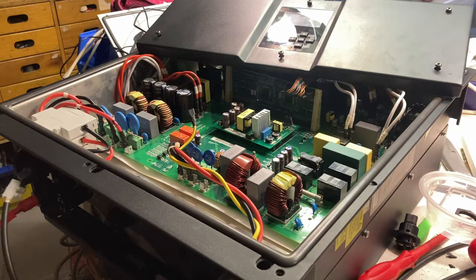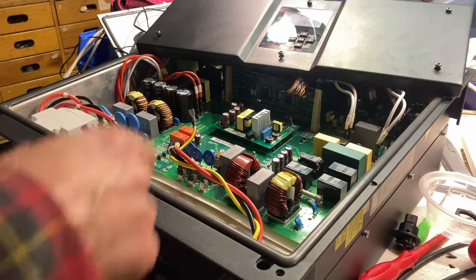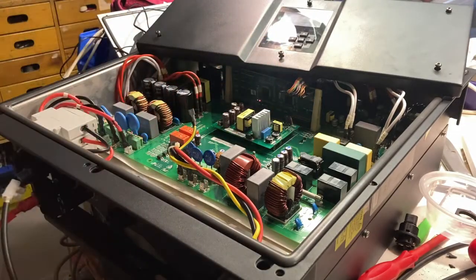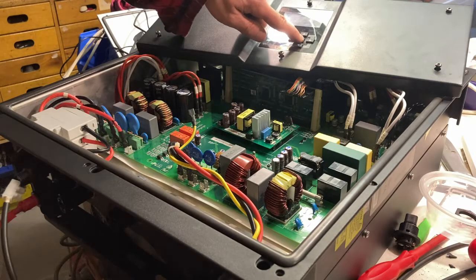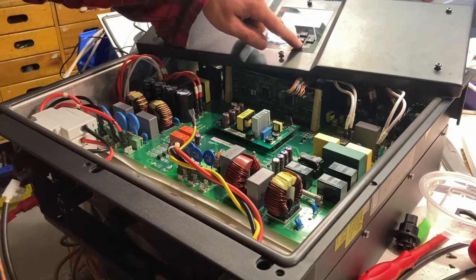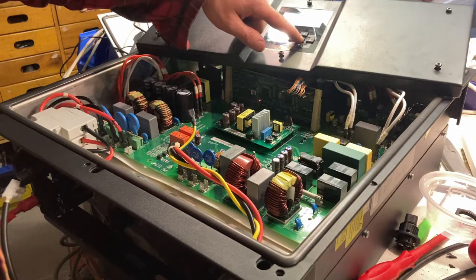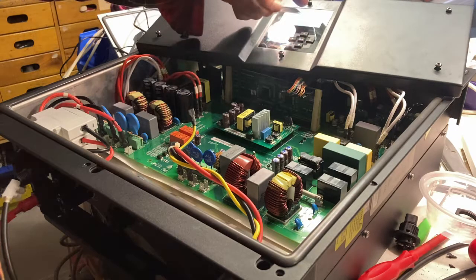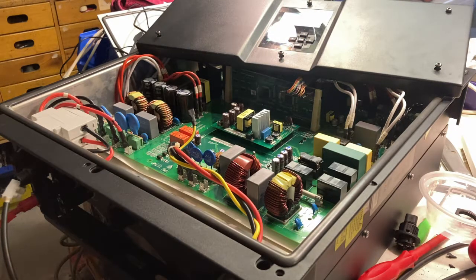So we have no earth. It's saying power, it's getting 226 volts from the inverter. There's a possibility that relay there was okay the whole time, and it was this relay. Now we've got the fault up again. Okay. Record info. Again, it's error 10, so we're getting earth leakage according to this.